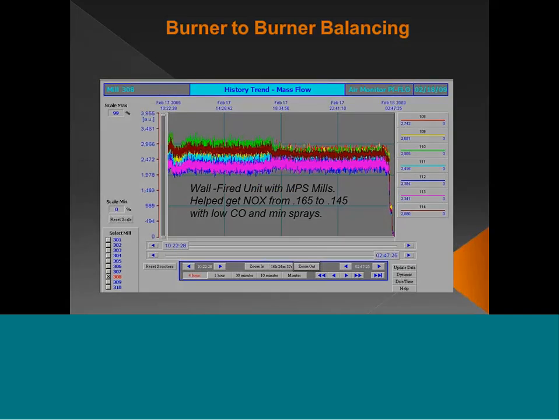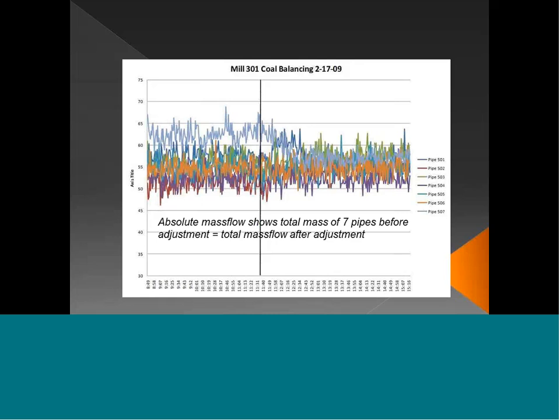Again, if we were to mathematically look at this data, I just want to point out again how important absolute, true mass flow measurement is. If we sum the pipes on the left of the line before we balance, we get a total mass, and if we sum on the right, we get the same total mass. We did not create nor destroy matter. We are measuring coal flow.